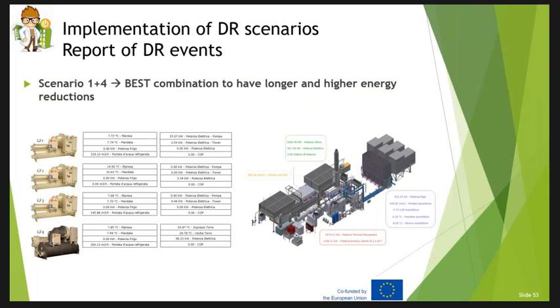After setting up all the scenarios and running them a few times, we also analyzed the response of the assets involved. I'm talking more about the electrical chillers, but also all the equipment cooled by them, so not just the air handling units, but also medical equipment like MRI. We found that the best combination to have a longer and higher energy reduction, so a better demand response, was to combine scenario 1 with scenario 4: lowering the electric energy of the chillers and switching the cooling generation from electric energy to gas consumption or district heating.